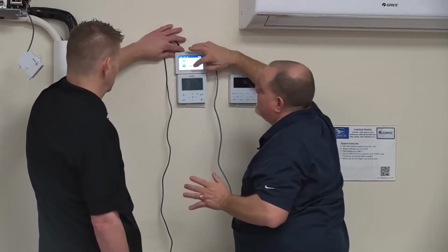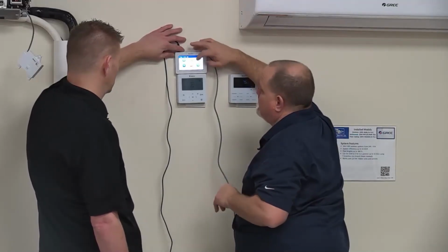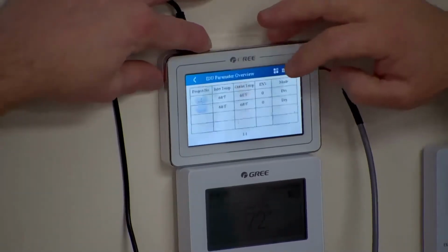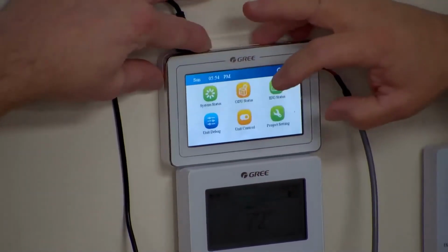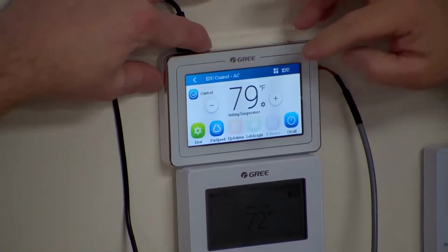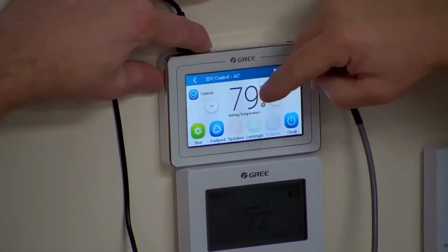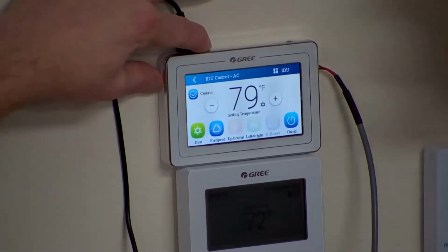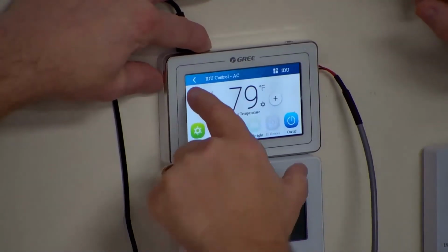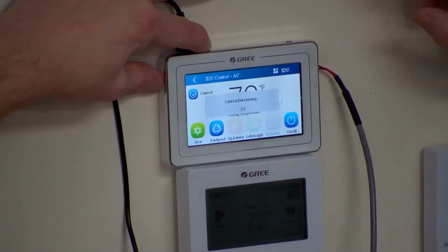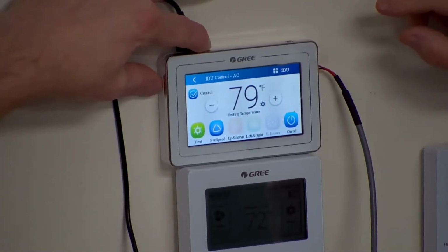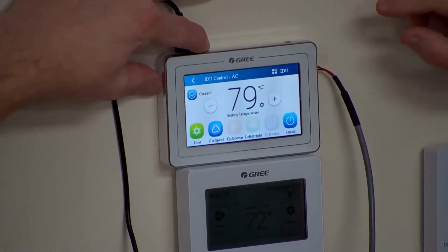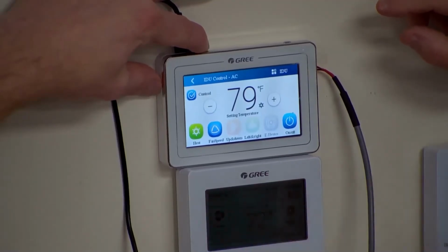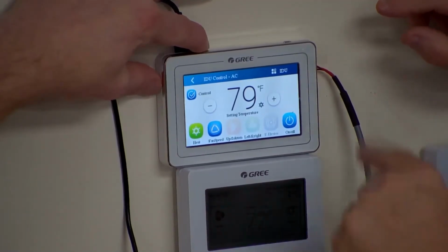Okay? All right, so now let's actually drive it on, and we can look at some status. So let's go to indoor unit. Oh, not indoor unit status, sorry. Unit control, indoor units, heat mode. I'm going to set it to 79 degrees. So now, in order to send the command, I've got to hit the check mark. Now it just sent the signal. Unit instantly came on. So it's overridden what the controllers are saying and just told this machine to run.